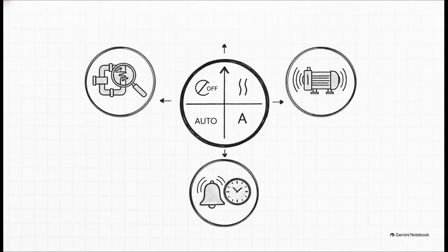You're going to spend a lot of your troubleshooting time staring at the control cabinet, so you need to know these modes inside and out. Auto is your normal operation. It relies entirely on those pressure switches we just talked about cleaning. Run actually bypasses those switches, forcing the pump to run independently. This is awesome for isolating a mechanical issue from a sensor issue. And don't forget the alarm function. Cabinets should be preset to trigger an alert if the pump runs continuously for 10 minutes. If that goes off, it's signaling a total failure to build a vacuum.